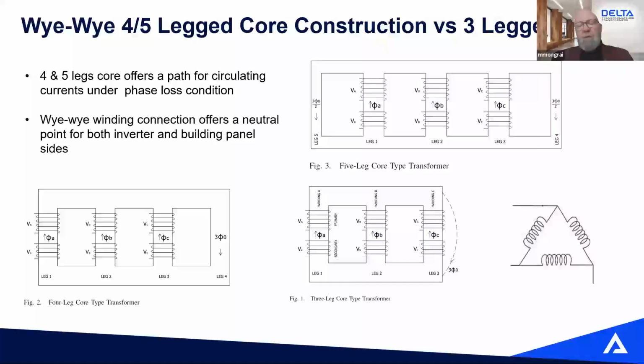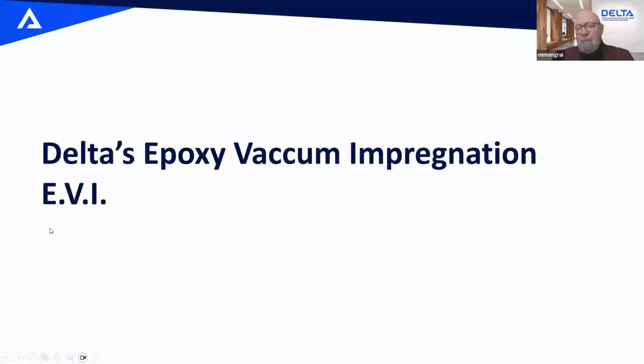We don't see lots of systems with a standard three-legged core. We do see it, but most of the time it's going to be a four or five-legged core. Of course, adding that fourth or fifth leg will increase the size of the core. More material is going to need a larger enclosure. So there's a cost associated to that. And again, when you select your transformer, if you say, never mind, I'll still use a three-legged core standard transformer, if you lose a phase, you might end up frying your inverter and causing lots of damage to your system. So sometimes trying to save on your transformer can cause lots of costly dollars down the road.